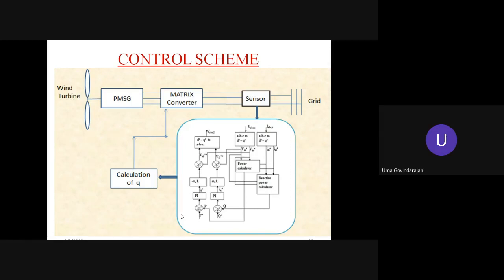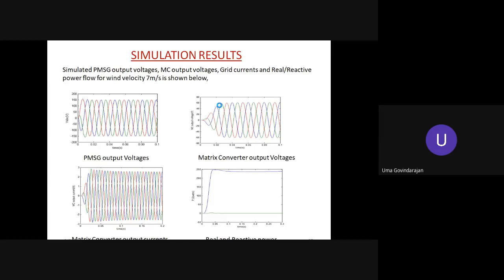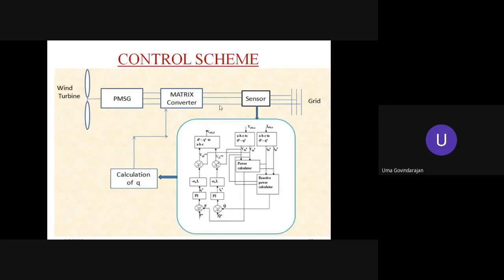Why I am telling you about the real and reactive power is that when you look into the connection of the converter to the grid, at the grid interface, if it is on the distribution end, this low power converter is like a rooftop low power unit normally put on the distribution side. In that case, whatever active power is harnessed from the wind turbine has to be connected into the grid. So at this interconnection point, with the power injection, we should not disturb the power quality at this interface point.